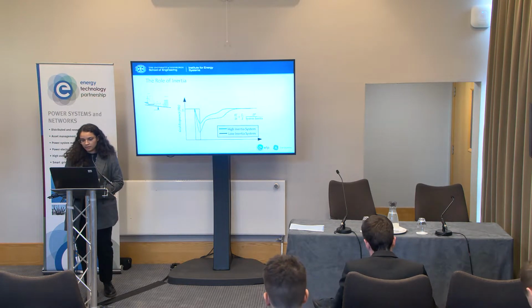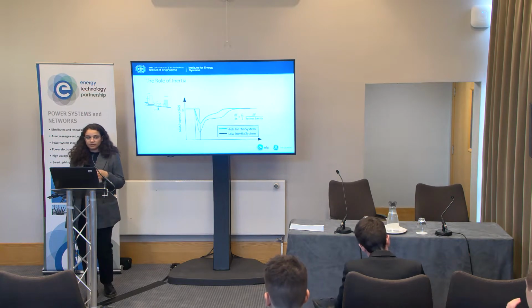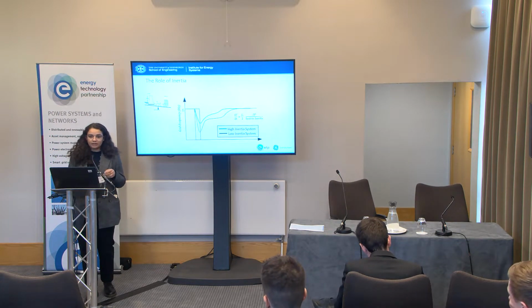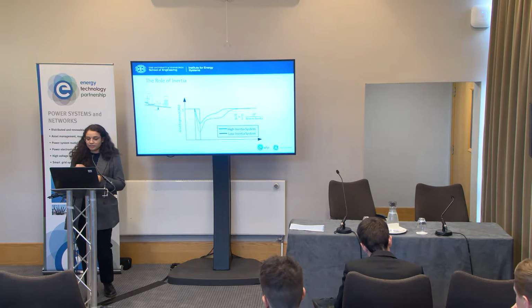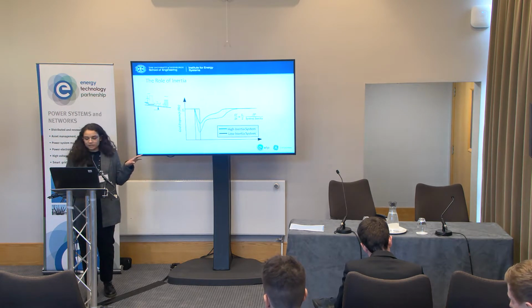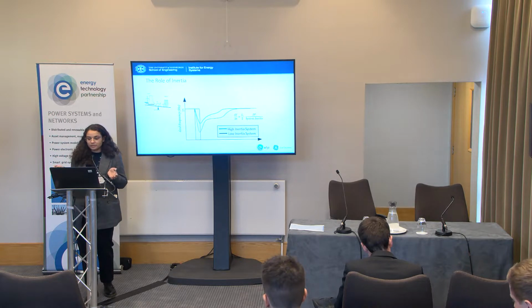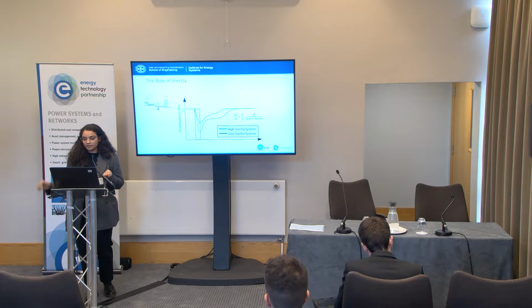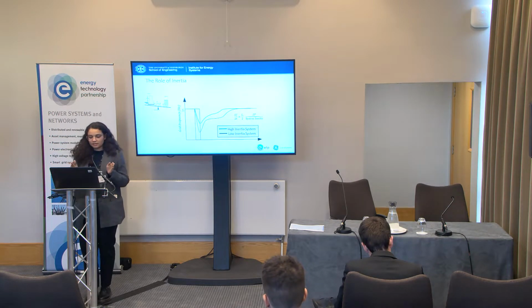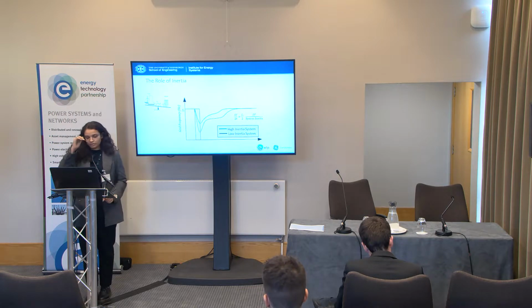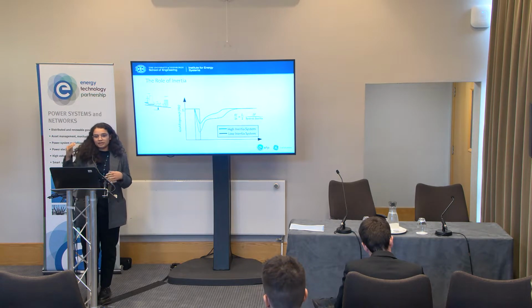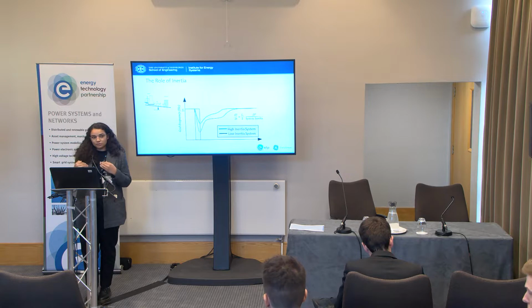And the amount of time that they have to work to stop that from happening depends on how high the amount of inertia connected to the system in that moment is. So this figure has a blue line which represents a high inertia system, and a black line representing a low inertia system. And the idea is, at the bottom of that fault, when the frequency is at its lowest, at that point the system operator has done something to fix the problem, but they need that time. So in a high inertia system, the frequency is much higher at that point than it is in a low inertia system.